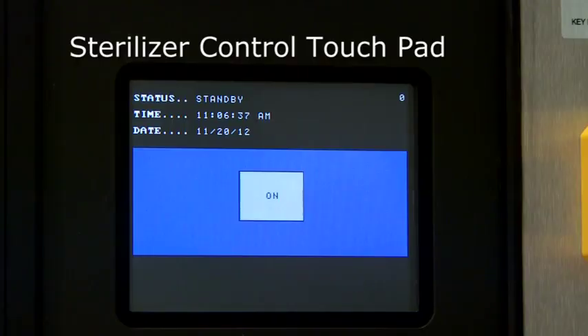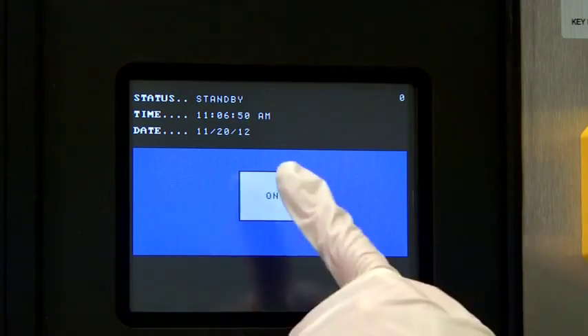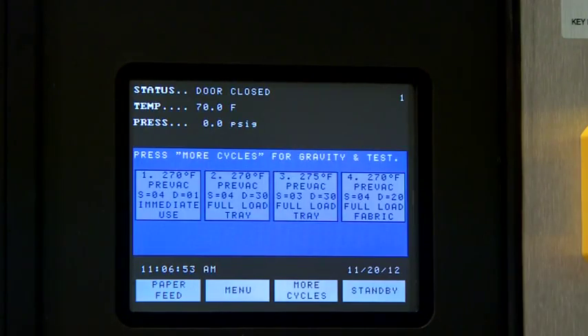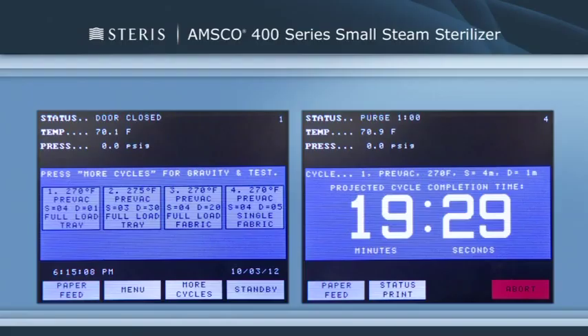The sterilizer control touchpad shows its standby mode usually at night when the sterilizer is not being operated. In this mode, steam is turned off and the machine cools, saving energy. It enters the operating mode when the on touchpad is pressed. This touchpad switches the sterilizer control between standby and ready conditions. You may notice screen reference numbers appearing in the upper right corner of each display. Numbers are used for reference only and do not relate to the operating sequence of the screen.